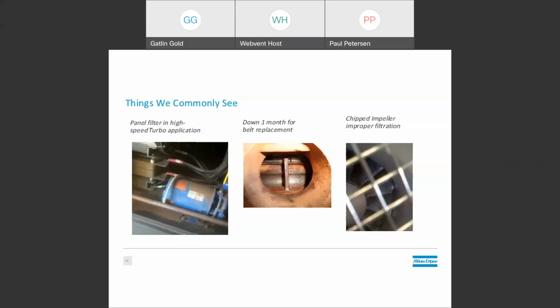The center picture is a picture of a lobe unit that I saw when I was on site, and they had it down for about a month because the belt had broken and they just hadn't had time to replace it. When they put the new belt on, the unit was locked up and they had to pull out the good old monkey wrench to get it moving again. And then here on the right, you can see what happened with a washable filter that was installed on a high-speed turbo unit. They washed the filter and put a few extra holes in it. The mud that had clogged up was actually tearing the filter apart when they washed it. So it was allowing larger particles to go through, and that was chipping high-speed impellers.